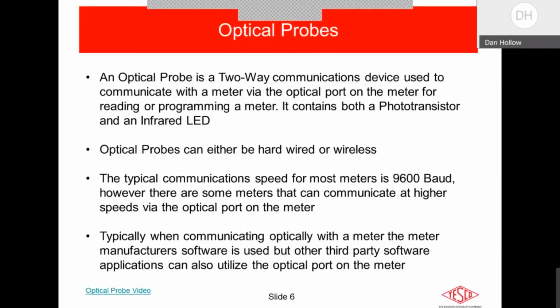The typical communication speed, and this has been this way for quite some time, is 9600 baud. That's the typical communication speed through an optical port. However, there are some meters that can communicate at higher speeds through the optical port. Not a lot of them that I've encountered. So that is the typical speed.